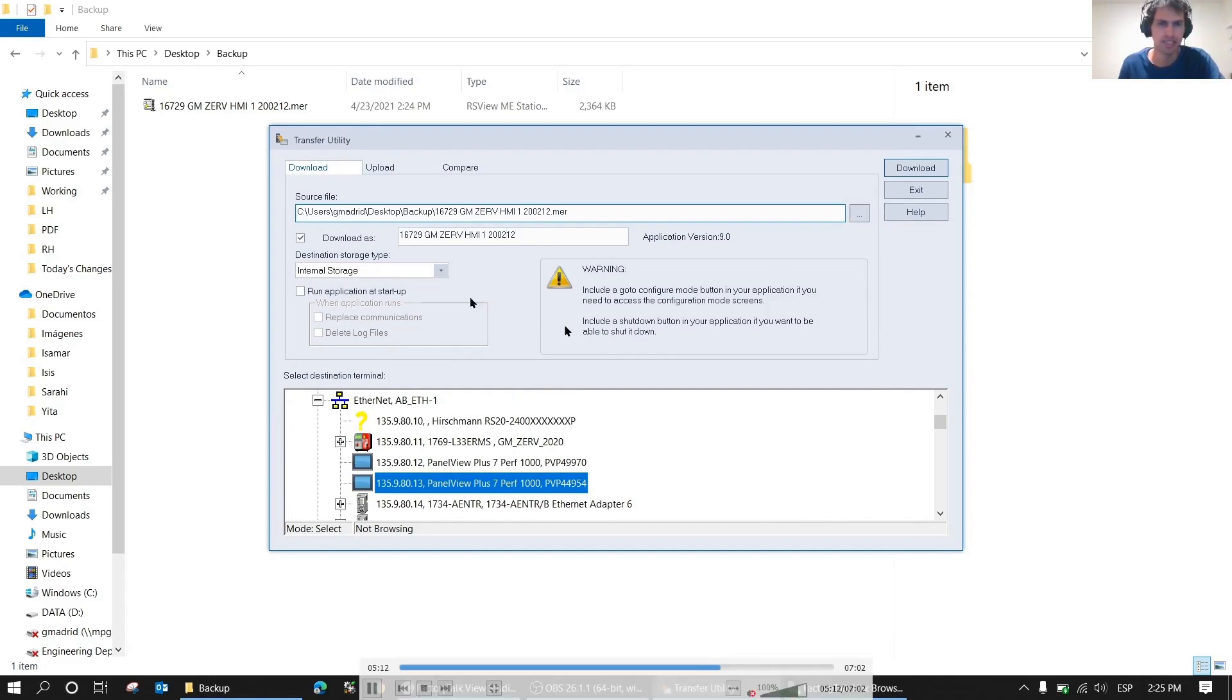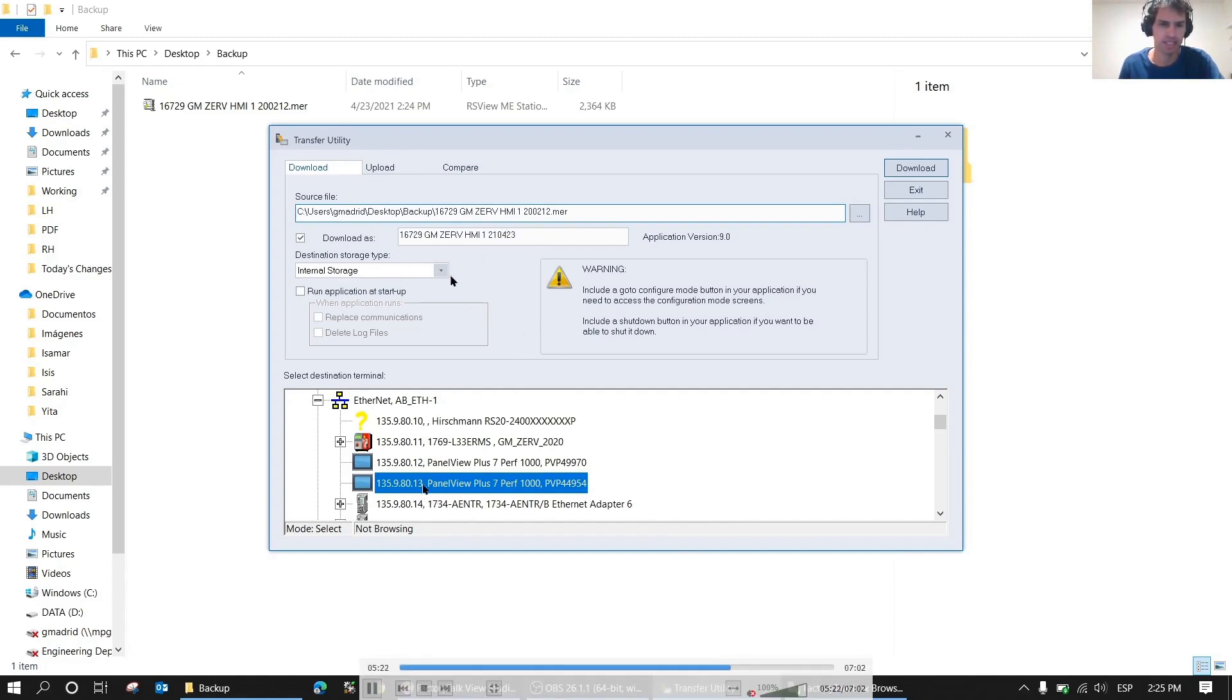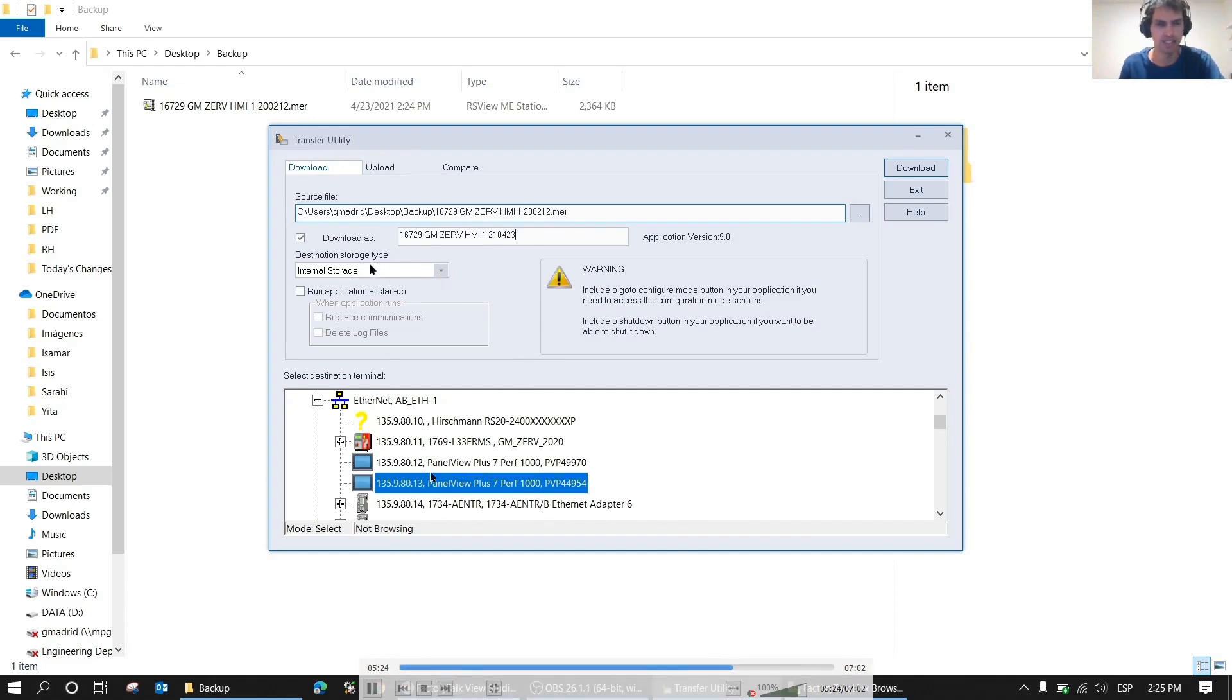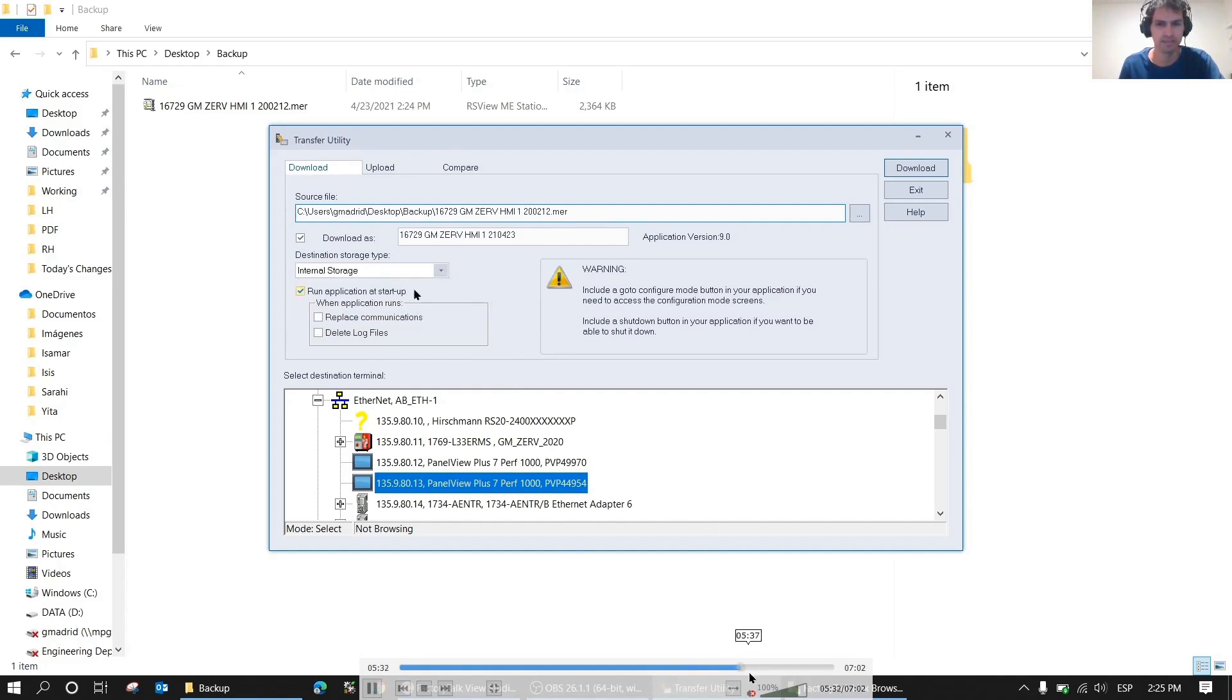Here I made a mistake. I downloaded it in PanelView 13 when I should have downloaded it in 12, because when I opened it, 13 was selected. So I downloaded it in 13 and then I downloaded it in 12. Then I simply went physically to the PanelView and deleted the one that wasn't needed.